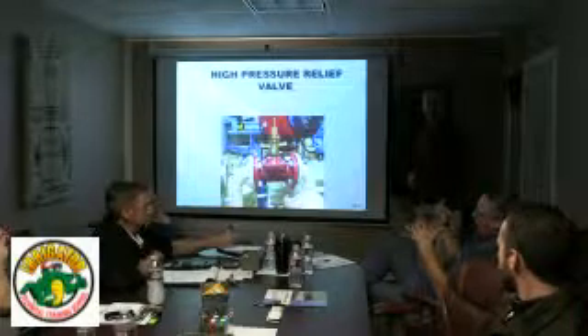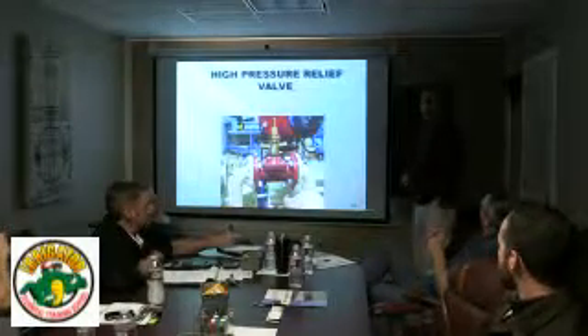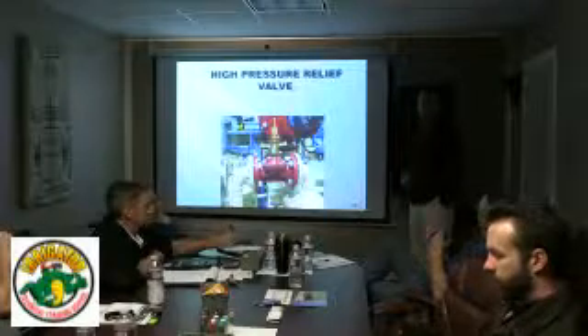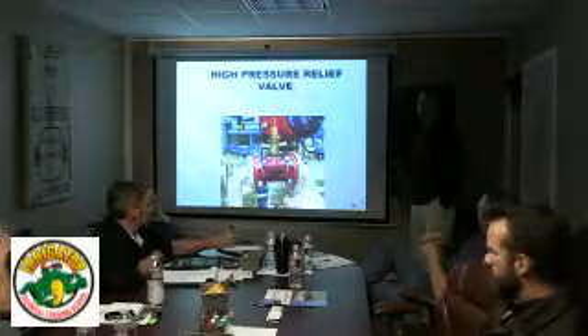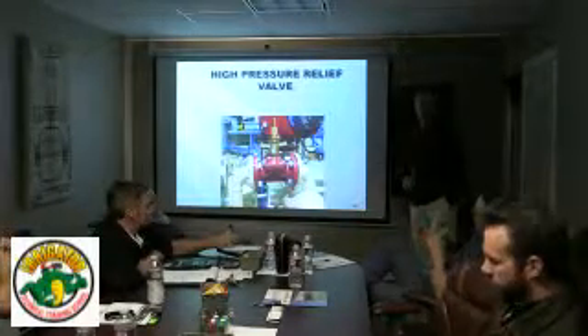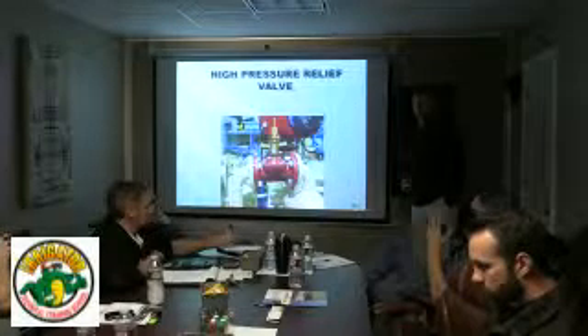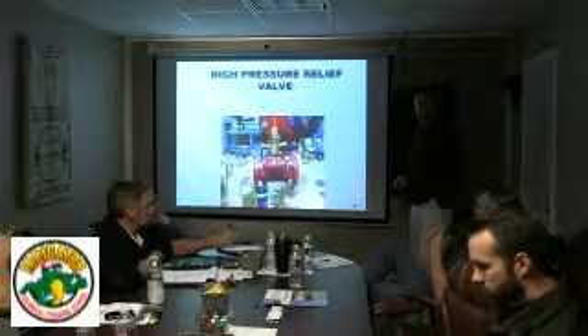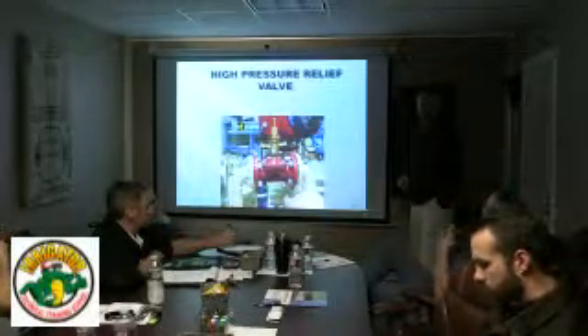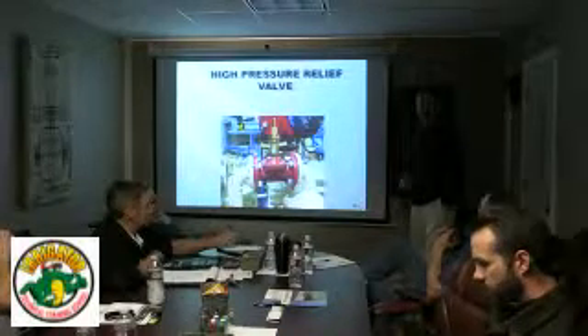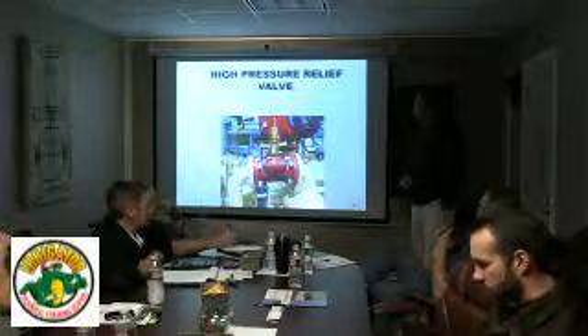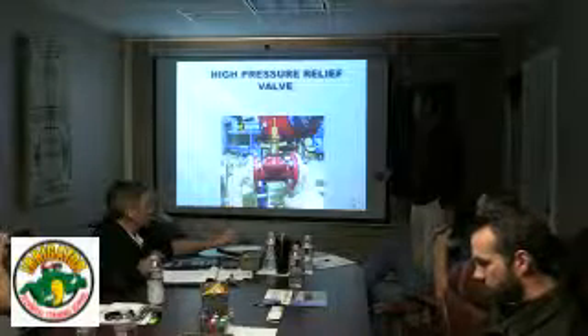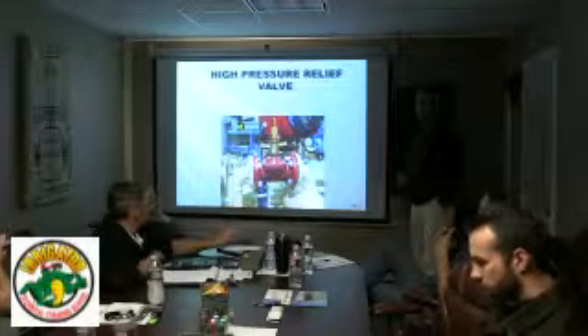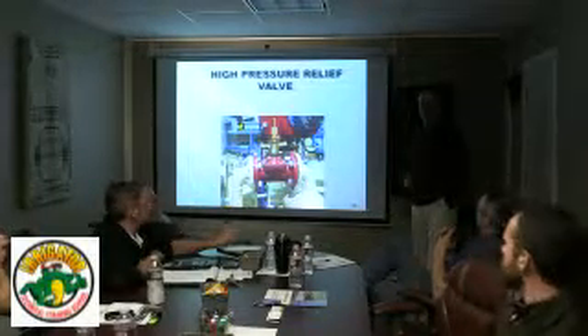Yeah, and they don't have much movement. And I think that probably has a lot to do with how often it gets used. On some of these, this probably never would activate if everything's normal. If it's not being used, I recommend even more strongly to take it apart, clean it and put it back together, even if you don't put a new kit in it once a year. And I have seen these rubber diaphragms get pretty hard, and then they won't flex much.